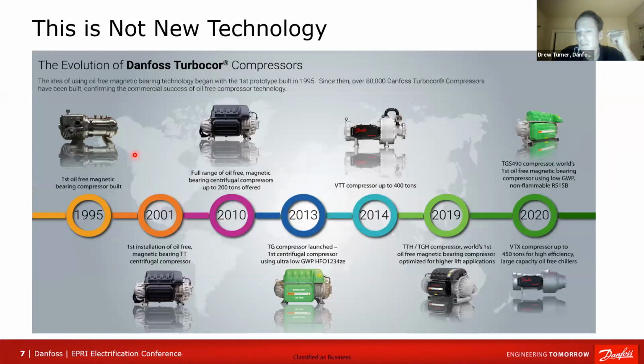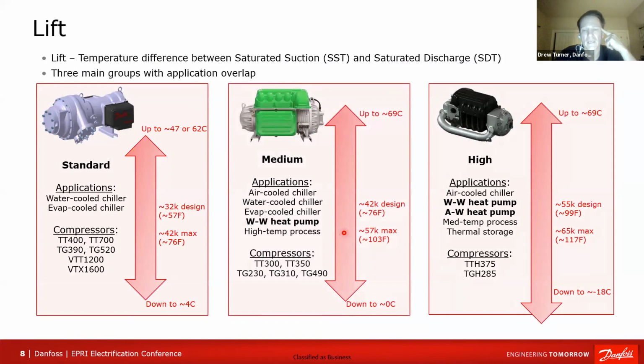The other point that we like to make is that Turbocore is not new. I already touched on this, talking about the history, but the first compressor was invented in 1995, first commercialized in 2001, and a full portfolio has been developed over those 25 years, or roughly 20 years since that first commercialization. That includes now, and this is where we get into the heat pump critical factors, when you look into a heat pump application, especially a larger industrial or commercial one, usually it's a combination of lift, or differential temperature and pressure, that needs to be met to have an optimized solution. And what that 25 years of evolution of the compressor portfolio has driven is that broad portfolio of optimized solutions.